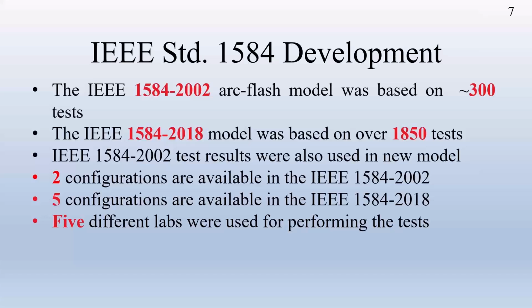Because the 2002 edition was a little bit rushed, the model was based on about 300 tests. For the 1584 2018, I have run more than 2,000 tests, but in some of the tests the arc did not sustain. So the useful information is about 1850 tests. The 2002 model only provided two configurations, and in 2018 we extended to 5 configurations.